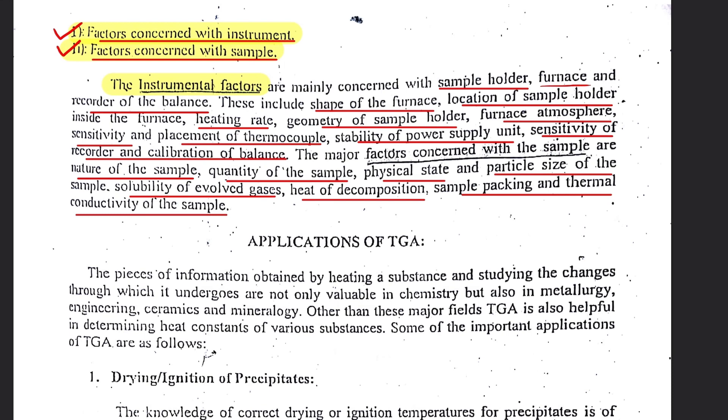Remember that these are two factors that if we take a reading of a single sample, it can have variations in that analysis. The variations due to the instrumental factors include the variations due to sample holder, due to the furnace and recorder of the balance, due to the shape of the furnace, due to the location of sample holder inside the furnace, heating rate at which we are heating from zero to five hundred or one thousand and which increments of heating we are using, similarly geometry of the sample holder, the furnace atmosphere, sensitivity and placement of thermocouple, stability of the power supply unit, sensitivity of the recorder, and calibration of the balance.